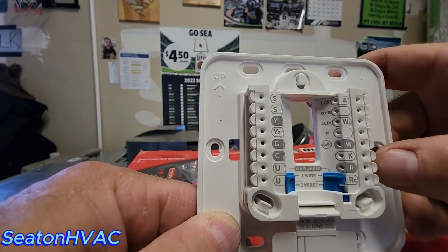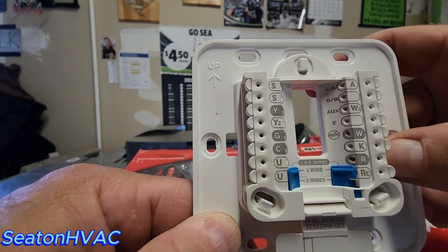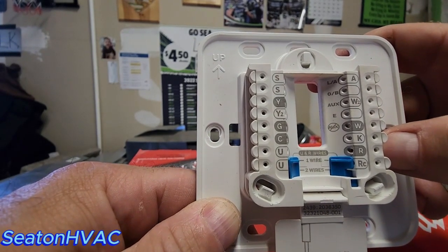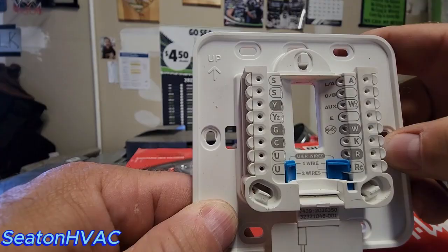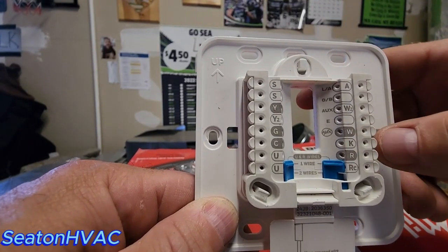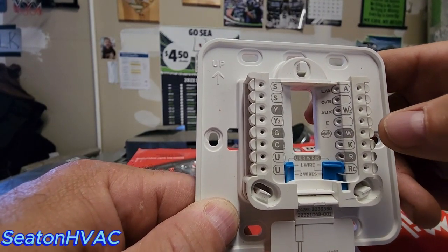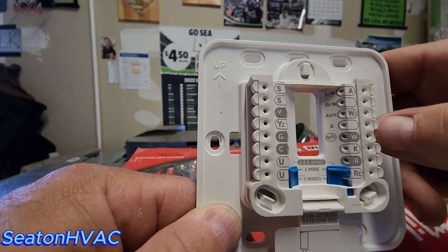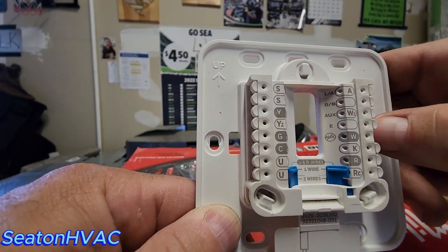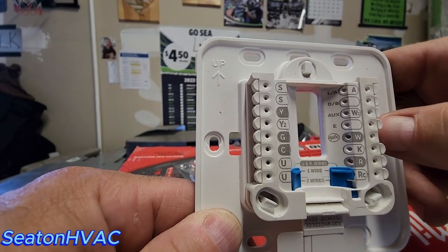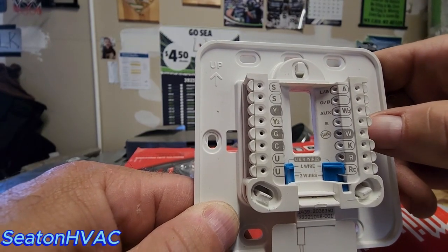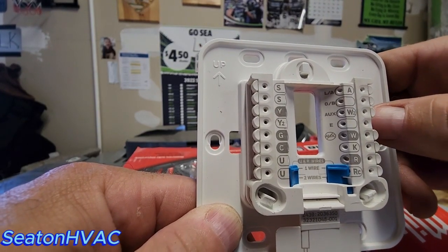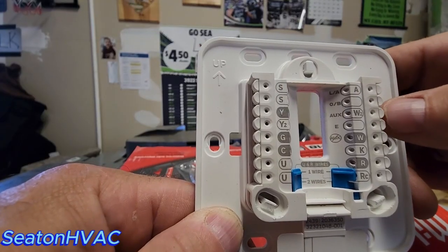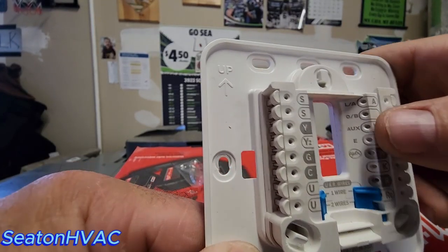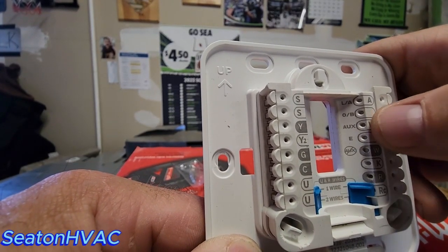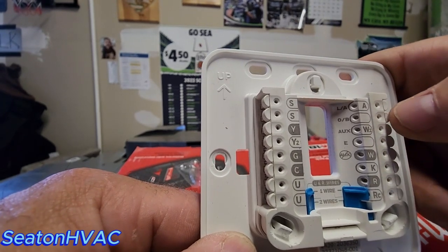And these are nice. These are little push-in terminals. You just push that down, push your 18-gauge thermostat wire in there, and then release that, and it catches, and your wire's locked in there. Make sure you push it in all the way. K is not used. W, that's not going to be used for heat pump unless it was a 2-stage. And actually, no, that's never going to be used for heat pump. Never mind. You have your E for emergency heat, and you can actually set this up in the programming to have E and auxiliary. See, it says E and auxiliary. You can have those powered at the same time, which you're going to have in most cases.